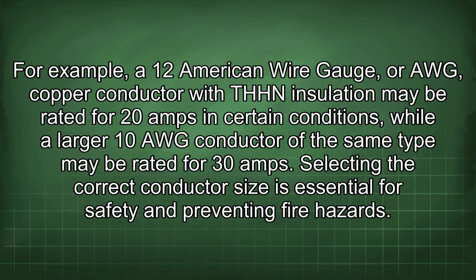For example, a 12 American wire gauge, or AWG, copper conductor with THHN insulation may be rated for 20 amps in certain conditions, while a larger 10 AWG conductor of the same type may be rated for 30 amps. Selecting the correct conductor size is essential for safety and preventing fire hazards.